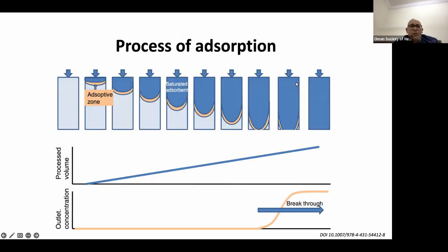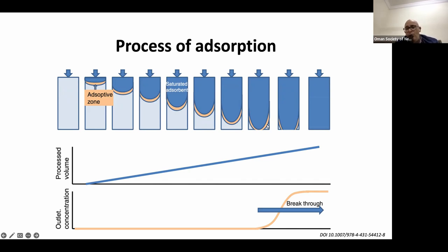Looking at the adsorption process in the graph: blood enters through the inlet and exits through the outlet, passing through the adsorptive zone. Over time, this zone begins to accumulate toxins and becomes saturated. After saturation, molecules continue to accumulate behind it until reaching the breakthrough point, at which time the blood is no longer being cleaned.